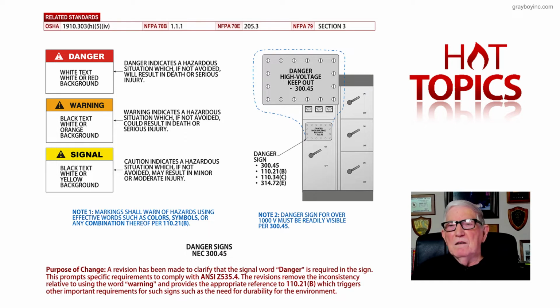But say now that the door had an orange warning sign on it and you opened it, you had to remove a second door to get into the energized components and so forth, then that's where your danger sign would be. And then, of course, the yellow is just for caution and where you want to caution somebody. I didn't show the blue label, which usually represents you're walking in and around a wet location. Be careful not to slip and fall.